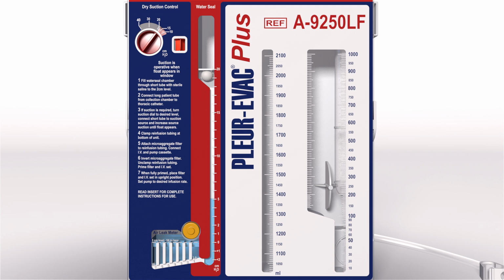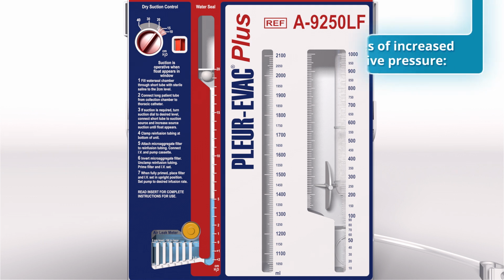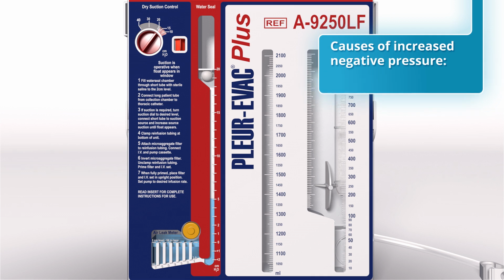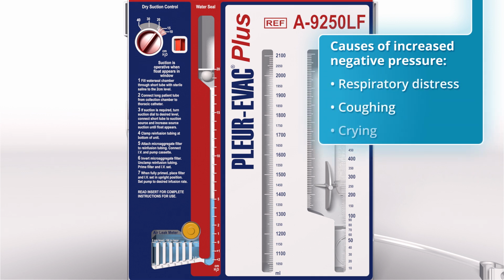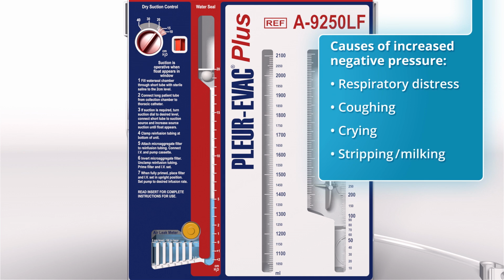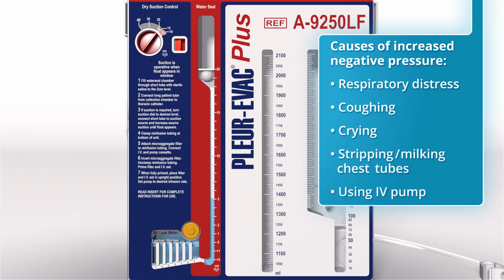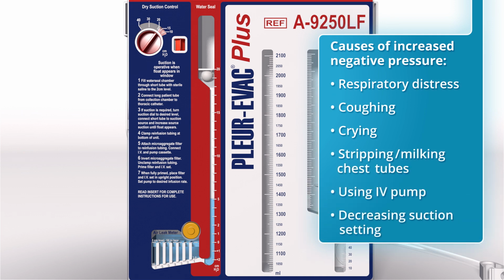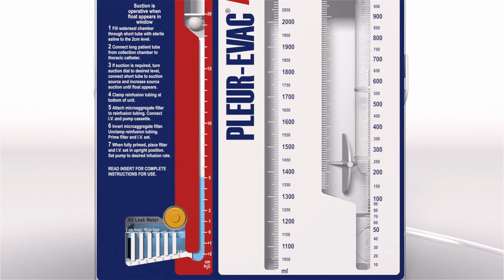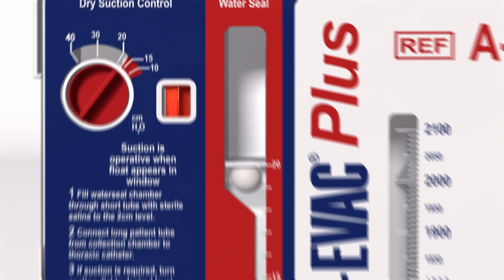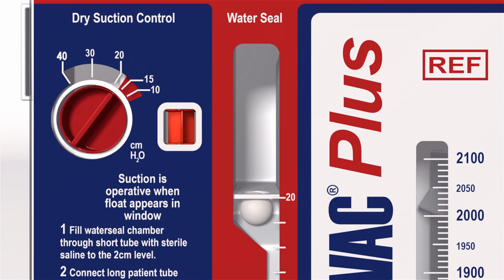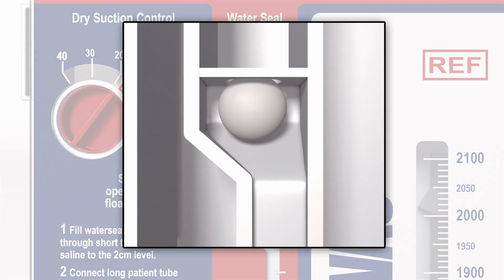There are instances when a patient will develop a high level of negative pressure. This may occur with respiratory distress, coughing, crying, or other factors such as stripping or milking the chest tubes, utilizing an IV pump, or changing from a higher to lower suction setting. When negativity increases, the water will rise in the water seal. If the water rises beyond the 20 centimeter level, the white float ball will rise, impeding the flow of water and preserving the water seal.